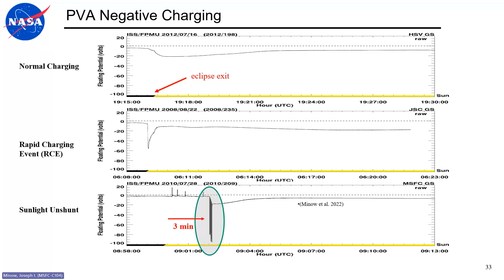Zooming in on that marked region, you see actually 8 different peaks, and every one of these is associated with one of the arrays on station. There are 8 arrays, numerically labeled 1A, 1B, 2A, 2B, and so on for all the various strings. When we had them do this experiment, we assumed they'd turn them all on at once, but they don't do it that way. They do them sequentially, about a second apart, and so you can see these charging peaks.